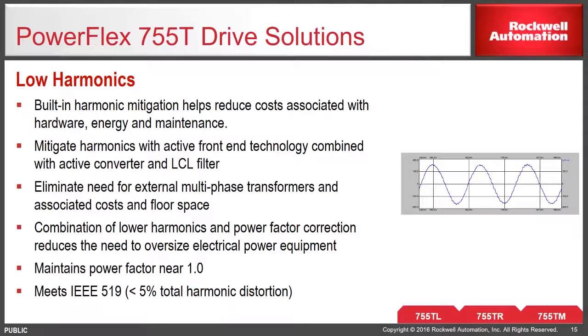It mitigates harmonics with an active front end. It eliminates the need for external multi-pulse transformers and associated costs and floor space. Combination of low harmonics and power factor correction reduces the need to oversize electrical power equipment. Maintains power factor near 1.0. It meets IEEE 519, that is, less than 5% total harmonic distortion.